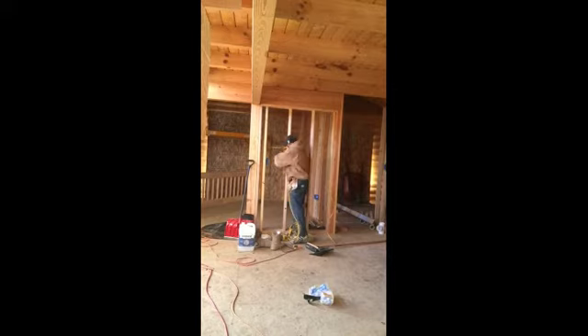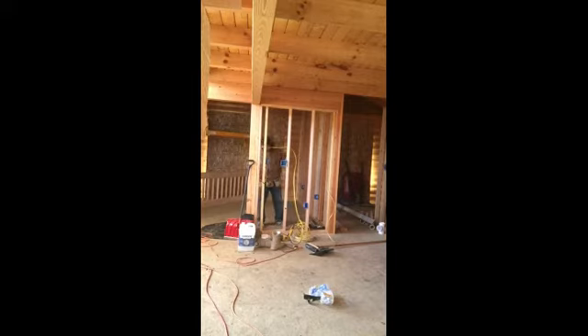Usually run it to the first plug in the room. That's what I recommend. You can run it to a switch, it doesn't matter. But you're going to have to wire the entire room off that one plug. So I say plug because you got more space to work off of. So you're going to have to snap the plastic knob off the back of the plug box, which you just nailed, usually about 18 inches from the floor, and run your wire through that hole, leaving a good 6 to 8 inches extra hanging outside of the electrical box that you nailed in.